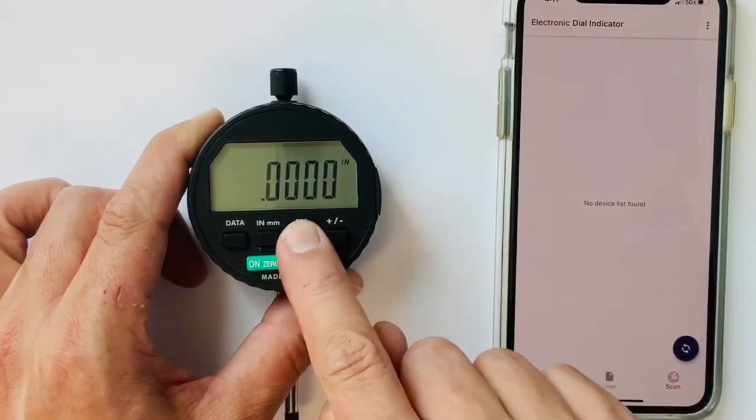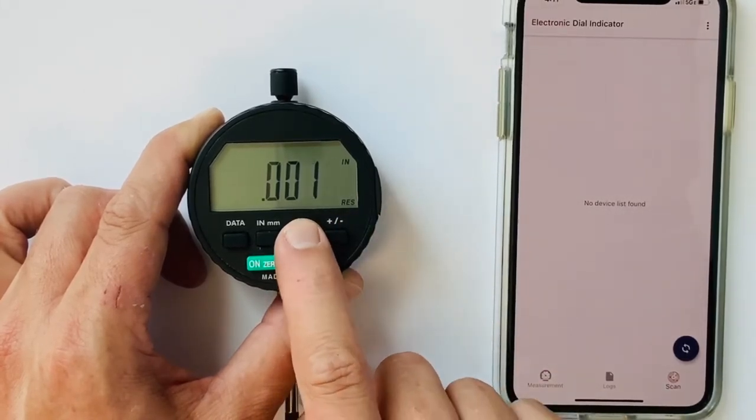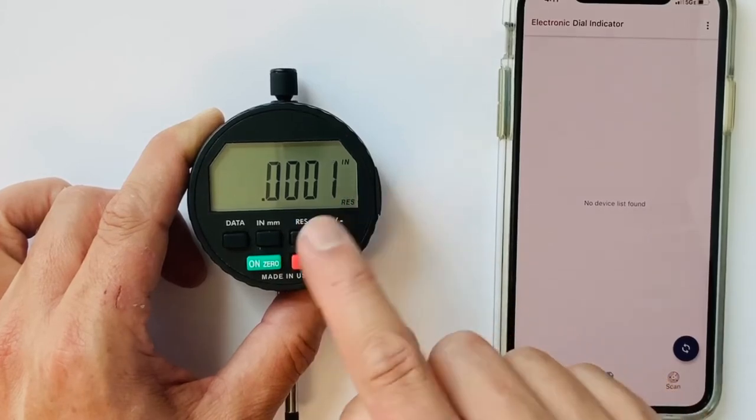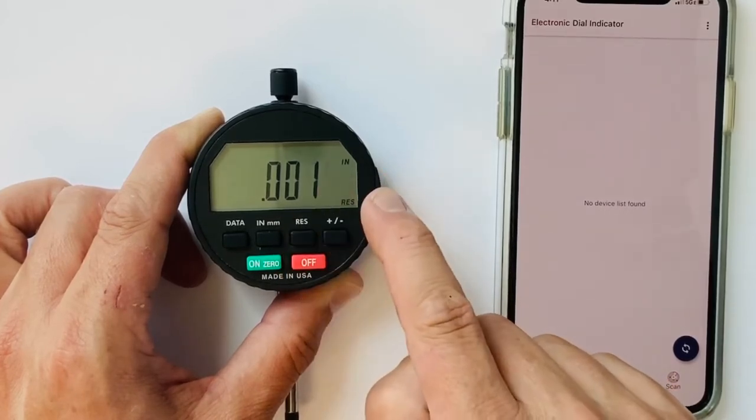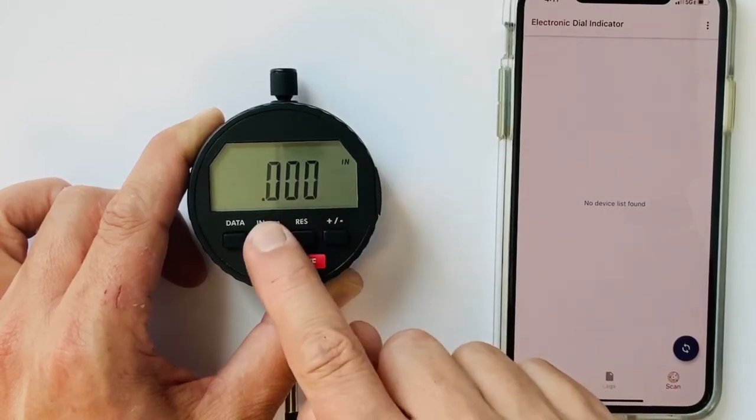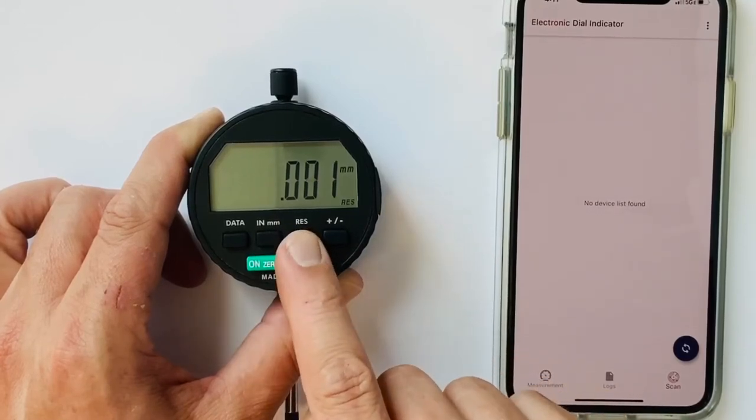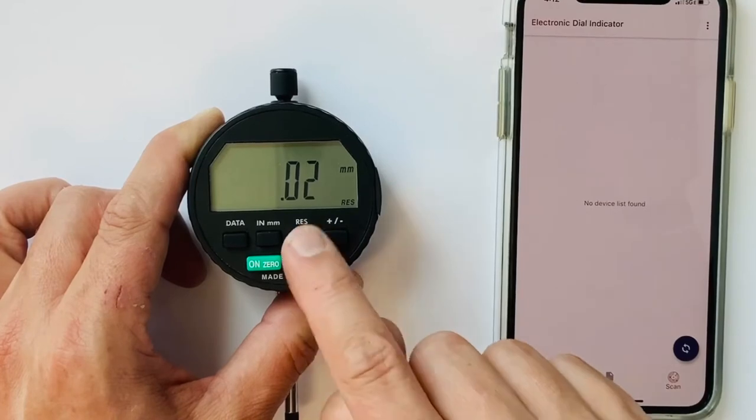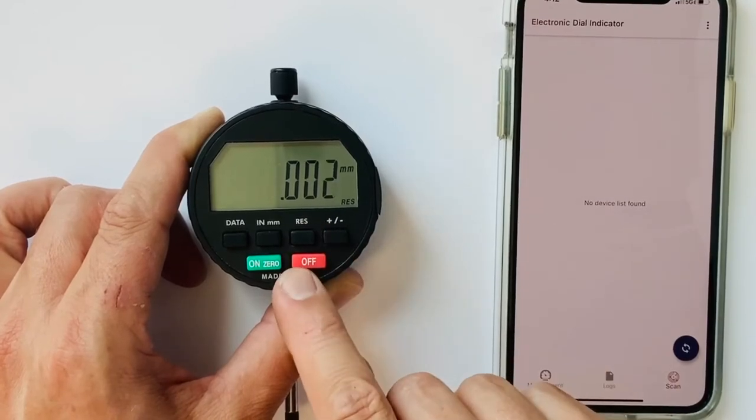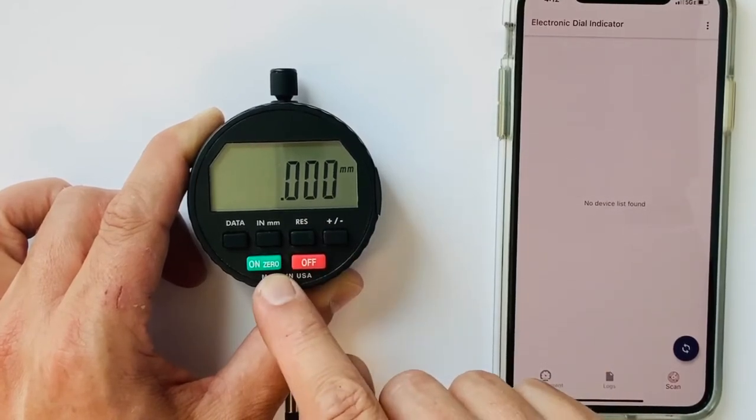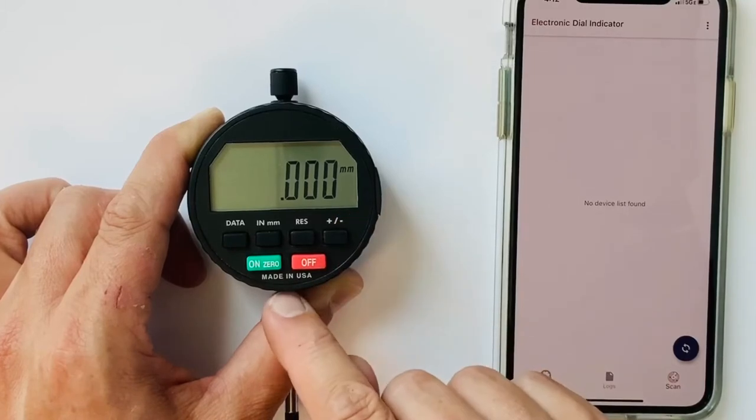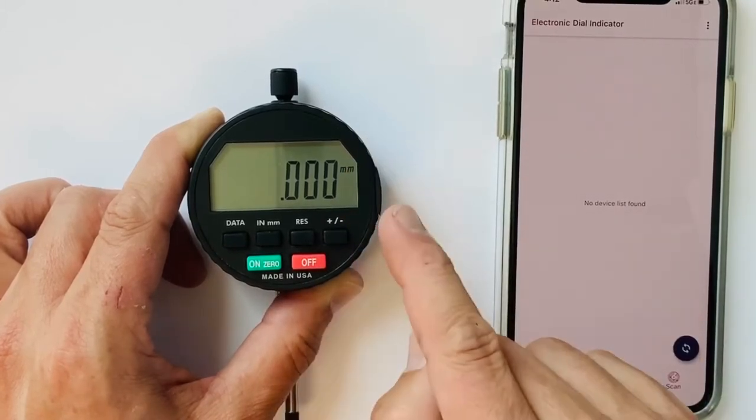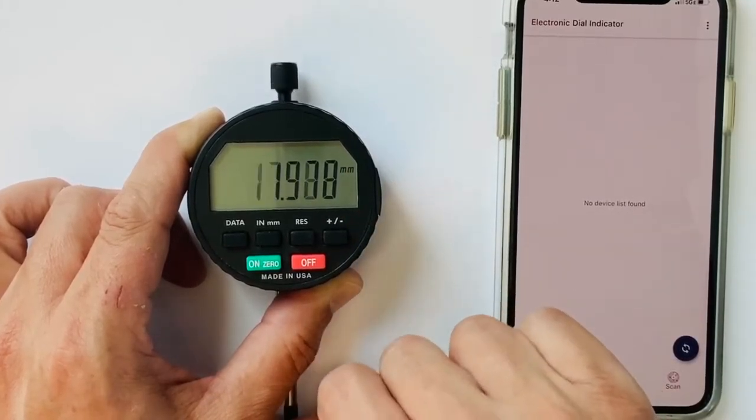This is a 50 millionths indicator. So I can go to 50 millionths, one tenth, five tenths, one thousandths, or in metric terms we can go to 1 micron, 2 micron, 10 micron, and 20 micron. Once again once I stop toggling it will time out and set it at the resolution I chose.